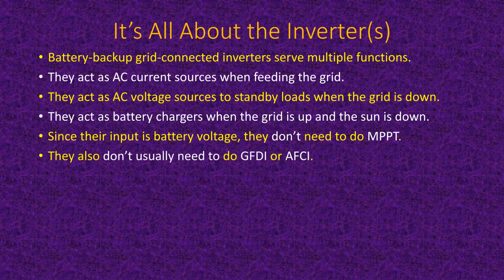Usually also, they don't have to do ground fault detection and interruption or arc fault circuit interruption, because those are functions that take place in other boxes, but now in many cases, they've been integrated into the main inverter for the system.